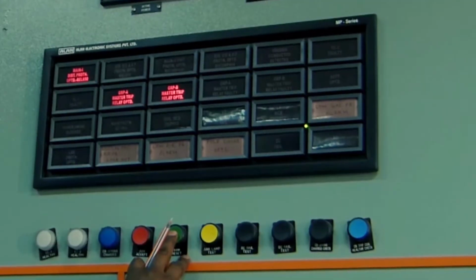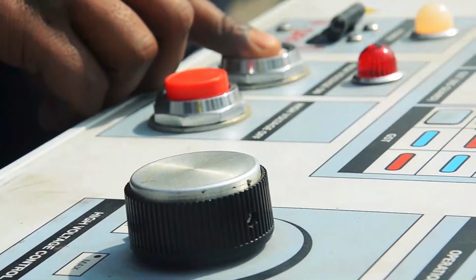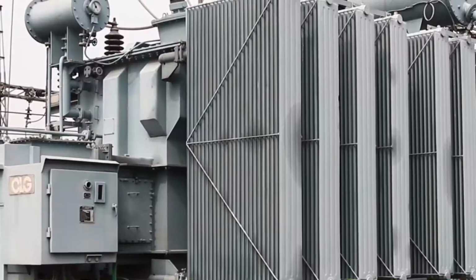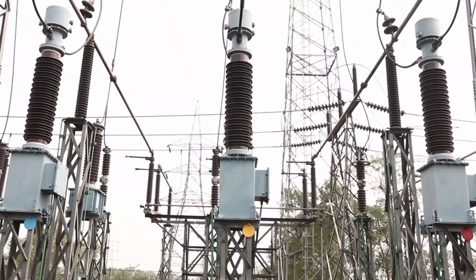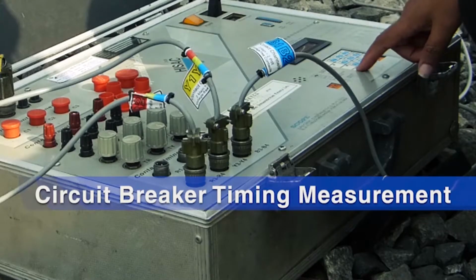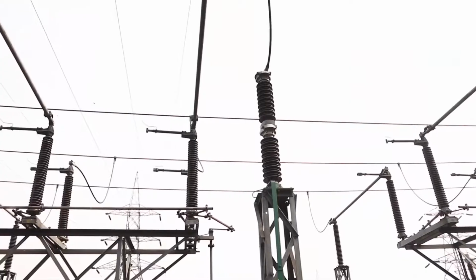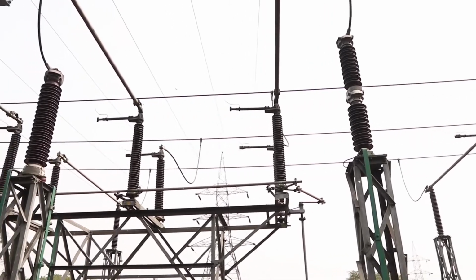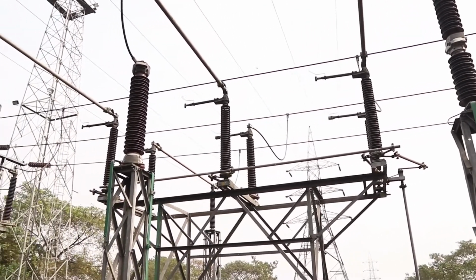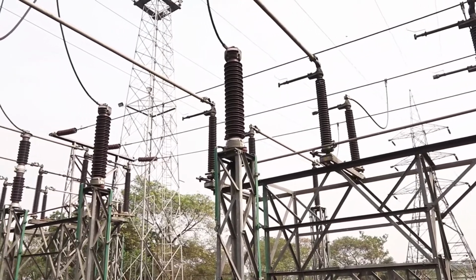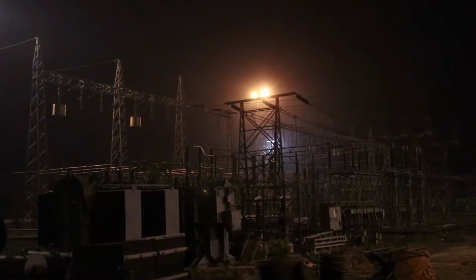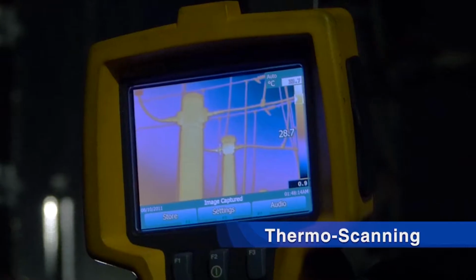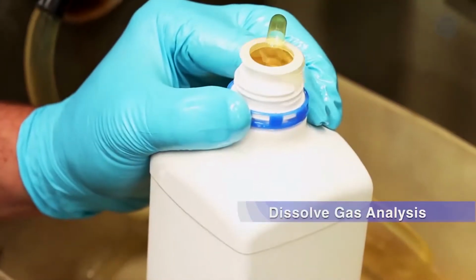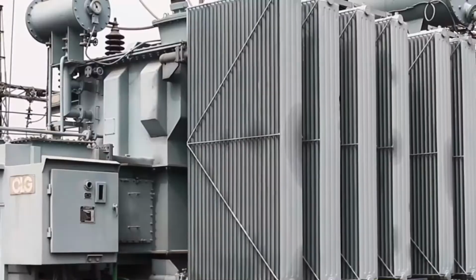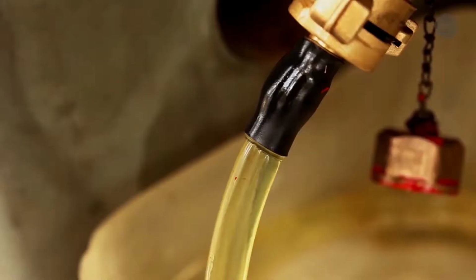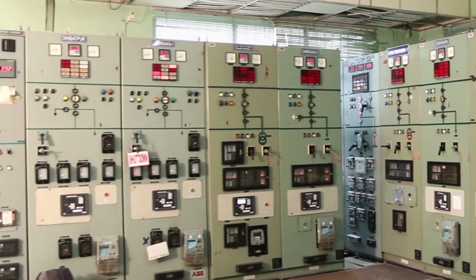Some of the new tests introduced are tan delta and capacitance measurement of power transformers and current transformers, circuit breaker timing measurement, contact resistance measurement, lightning arrestor (LA) third harmonic resistive leakage current measurement to check the healthiness of LA, thermal scanning of equipment and connectors, and dissolved gas analysis of transformer oil. With introduction of these activities, failure rate has been reduced to a great extent.